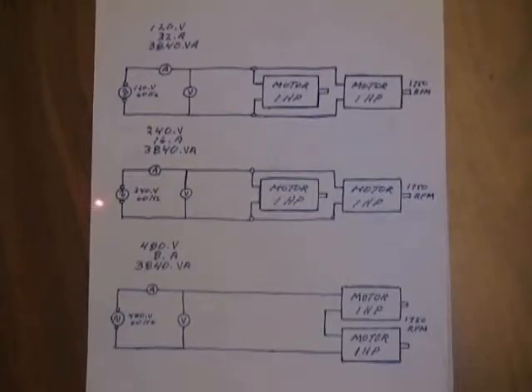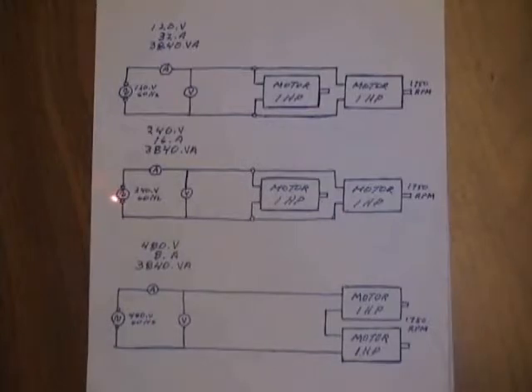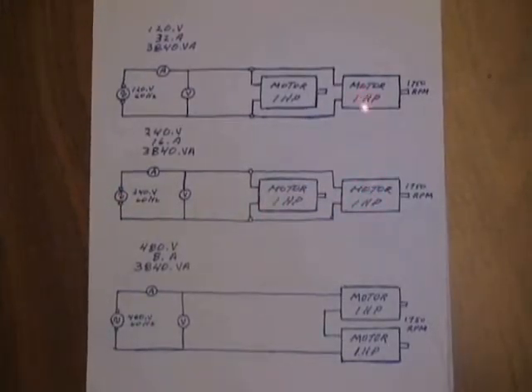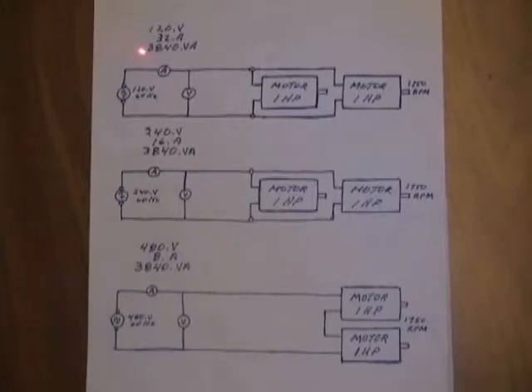Now, we can do the same, but with a source of 240 volts instead of 120 like before. And what we're going to see is that they are going to be running just like the ones above, but now they are connected to 240 volts. And so we will have to supply them with 240 volts, 16 amps, which is of course half the amount we saw before, and we are going to get the same total of volt amps, which is 3840 volt amps, just like before.